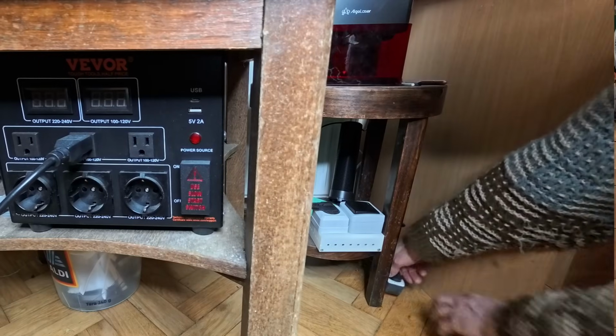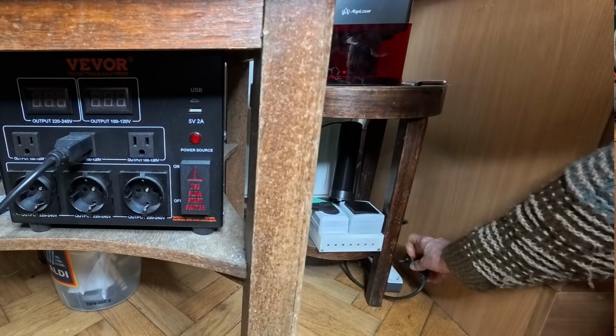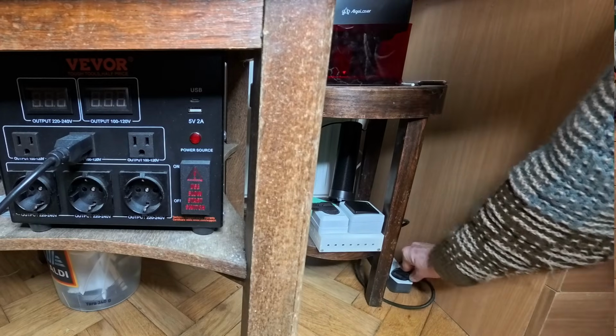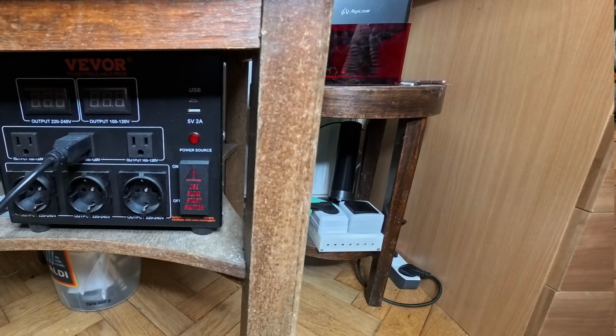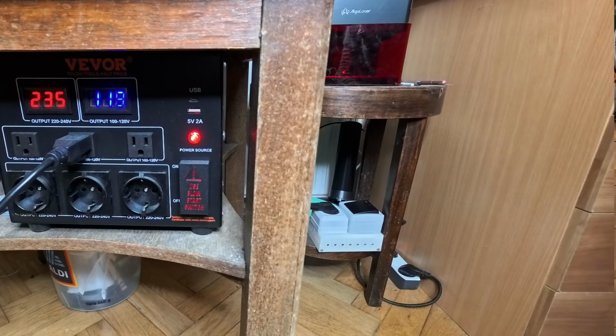When I reverse the plug to the correct orientation, the switch breaks the live wire right at the entrance, exactly after the fuses. The entire circuit is dead and the status light stays off. No markings needed, no guessing. The blinking light is a built-in foolproof indicator that tells us exactly when the system is plugged in safely. Don't we love it when a problem solves itself?